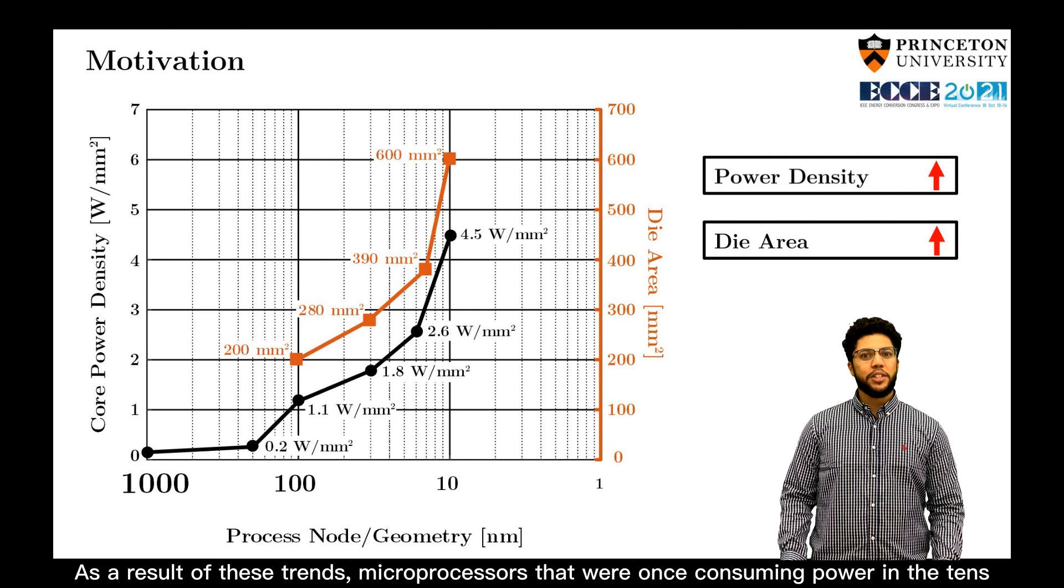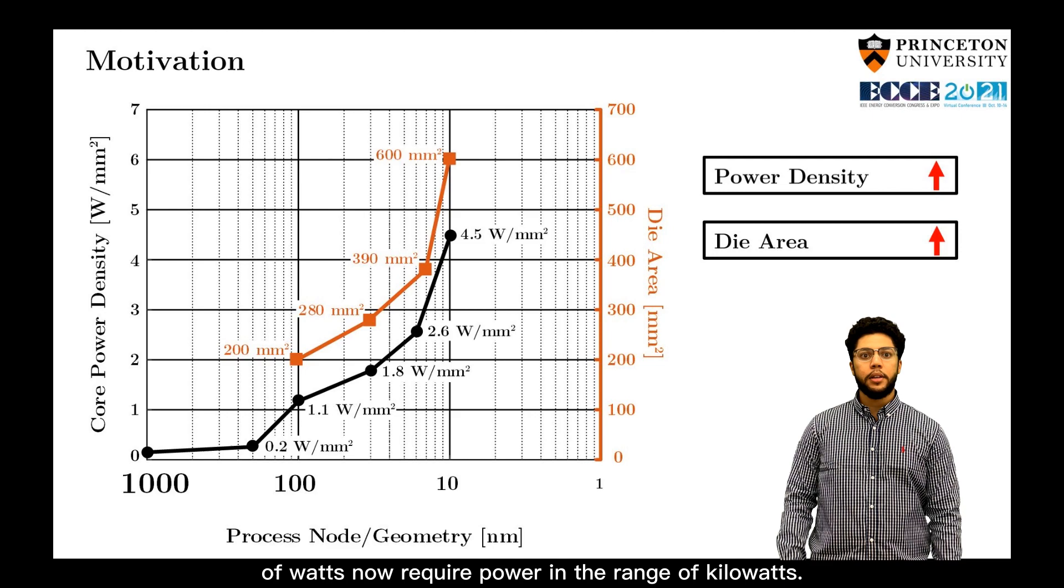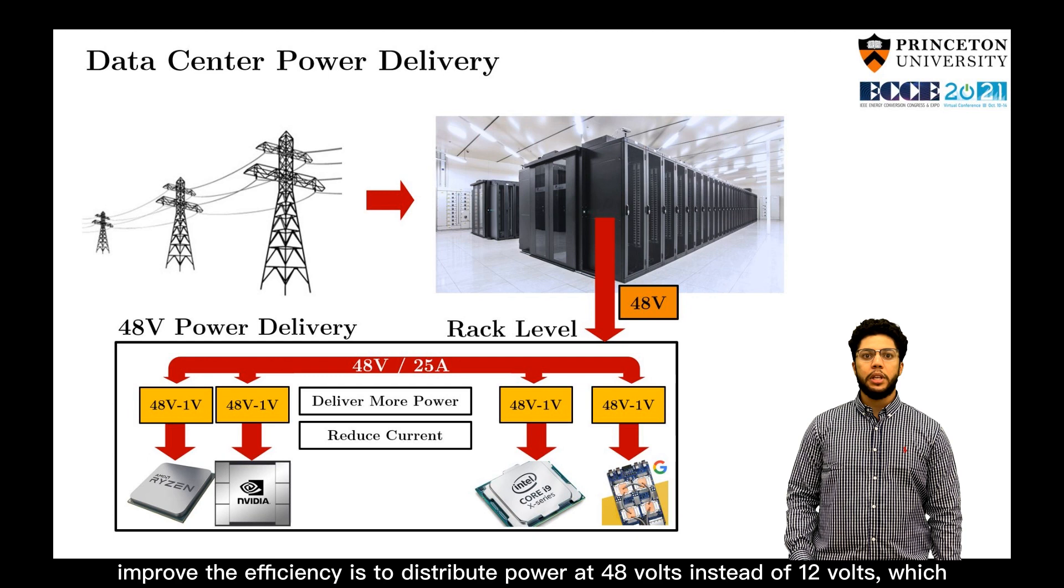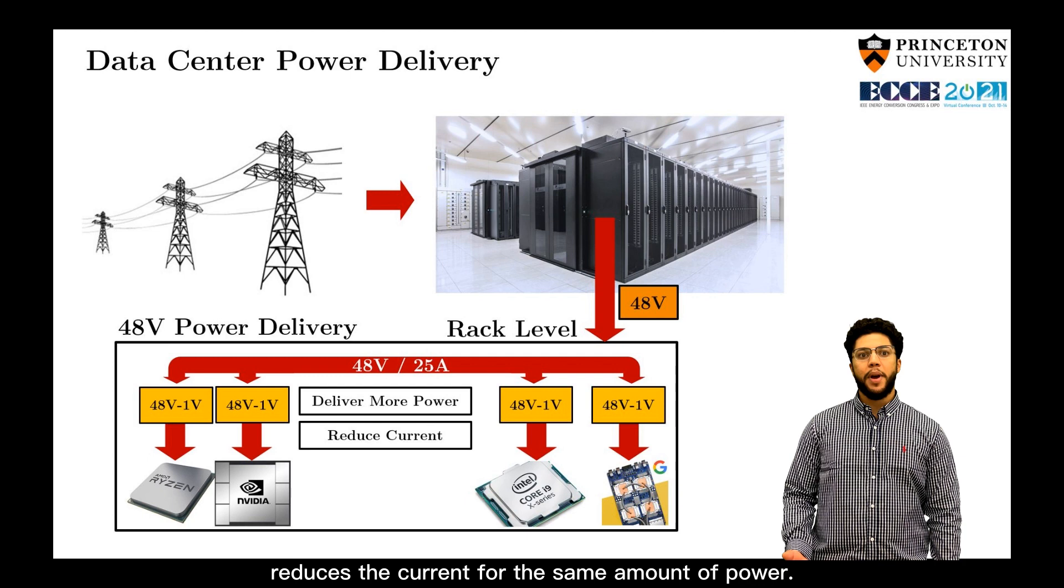As a result of these trends, microprocessors that were once consuming power in the tens of watts now require power in the range of kilowatts. An emerging trend to increase the amount of power delivered into data centers and improve the efficiency is to distribute power at 48 volts instead of 12 volts, which reduces the current for the same amount of power.